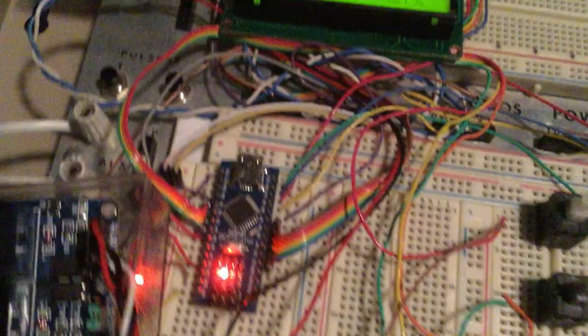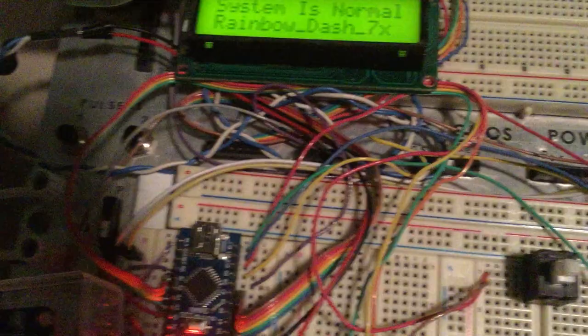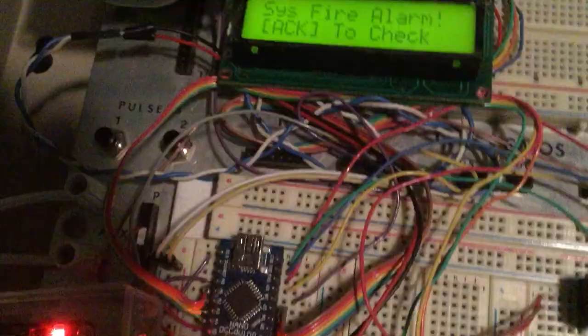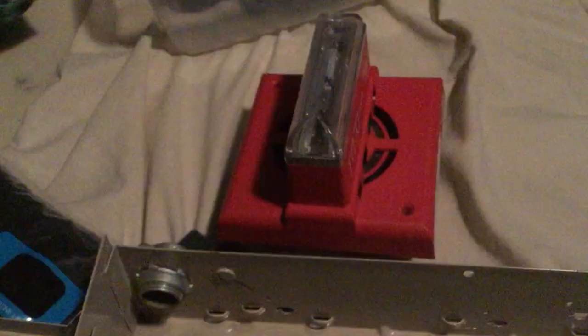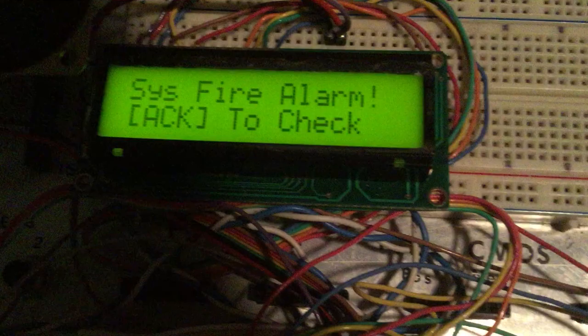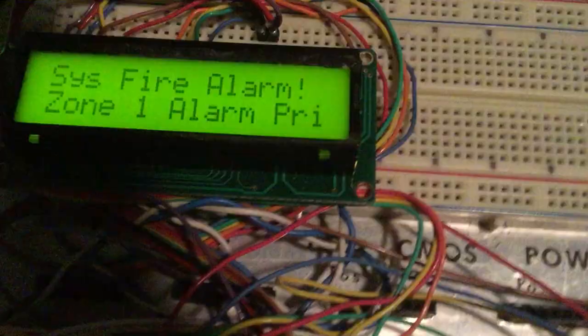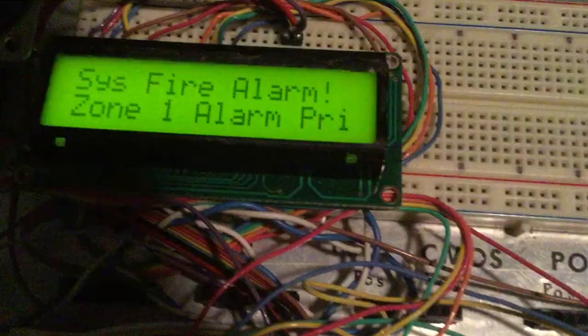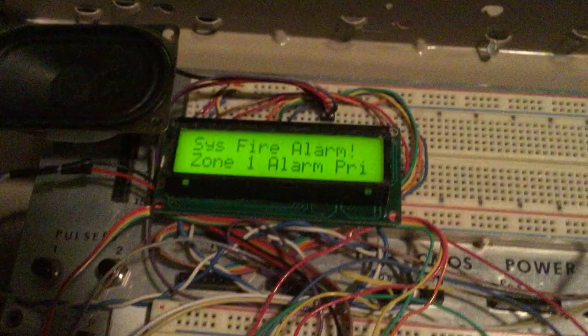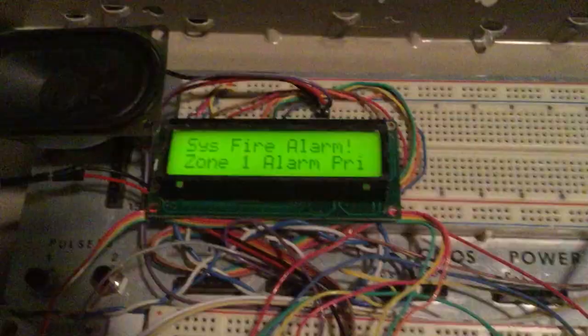Now I apologize, the alarm tone that this emits out of that speaker is quite loud. Here we go. We have system fire alarm, acknowledge to check. So I press that. Zone 1 alarm primary. That will be for a 2-stage operation. It'll say secondary once I get the 2-stage setup. That's pretty much just like a verification. But for now it's just going to say primary.